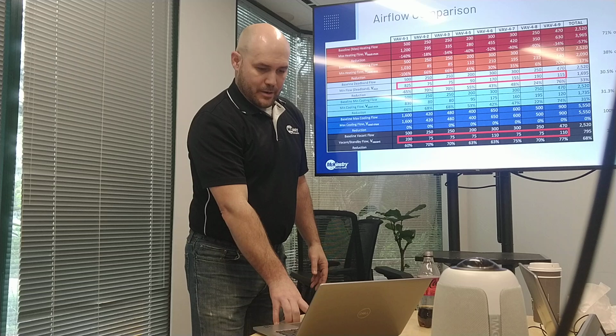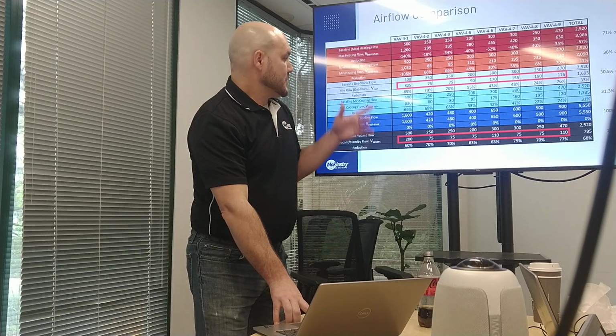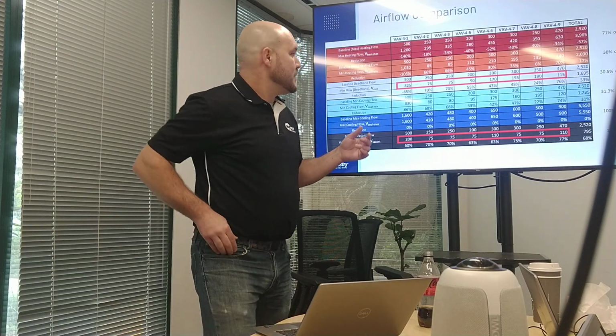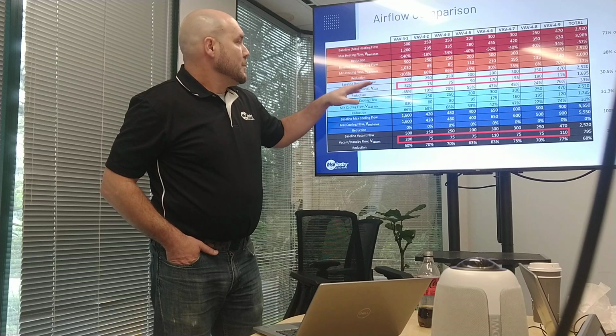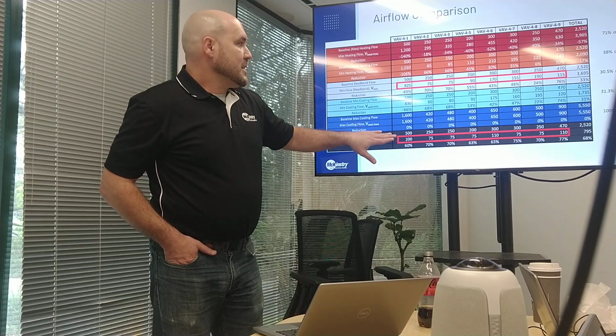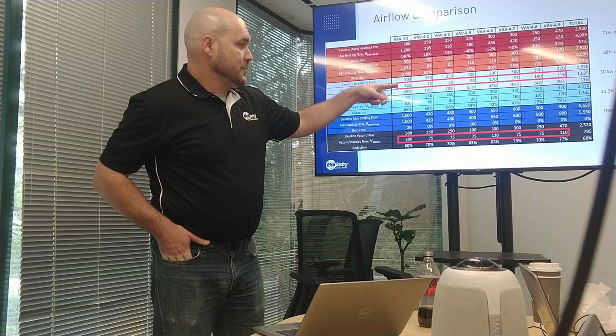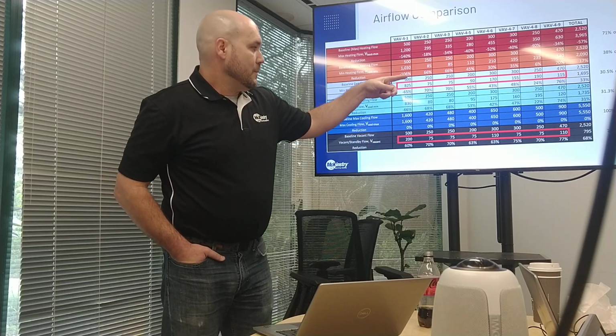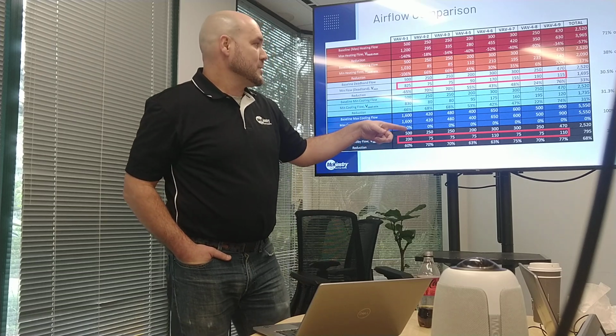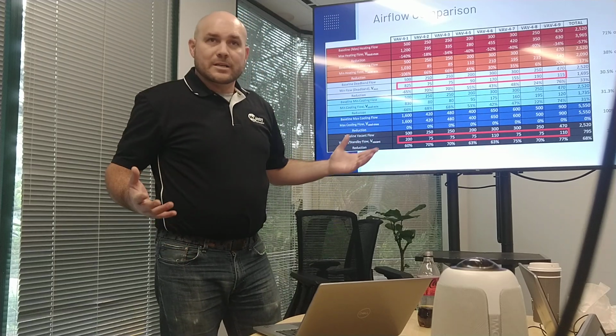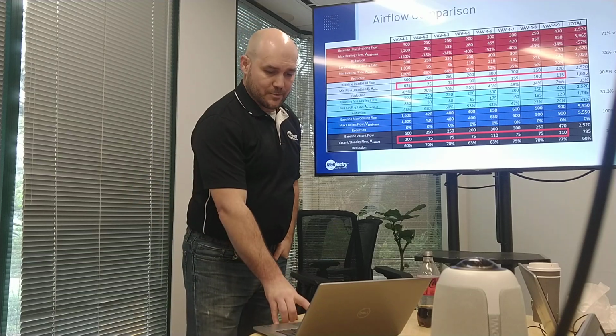Yeah, it's just comparing the differences. Whoop, didn't mean to do that. No, it was touch sensitive. But yeah, so the minimums between just deadband and the baseline, there's a huge reduction here. You go from 825 down to 200. A lot of these are similar, and that tells you that the limit is more dictated by the size of the box. But going from 170 down to 110, 155 down to 75, 190 down to 75, those aren't modest reductions, percentage-wise. Those could be pretty significant.